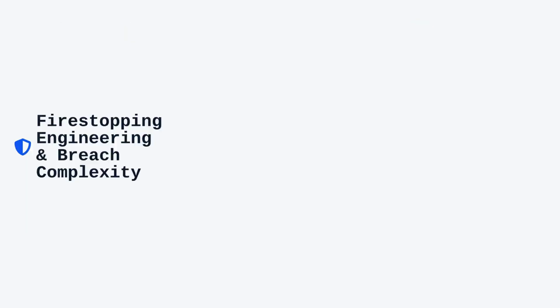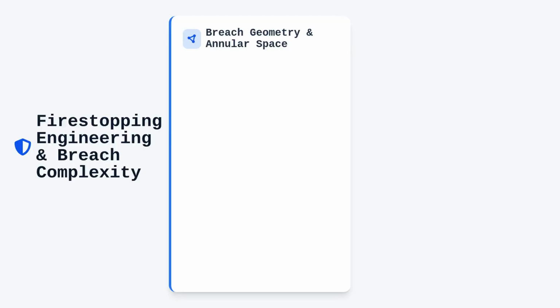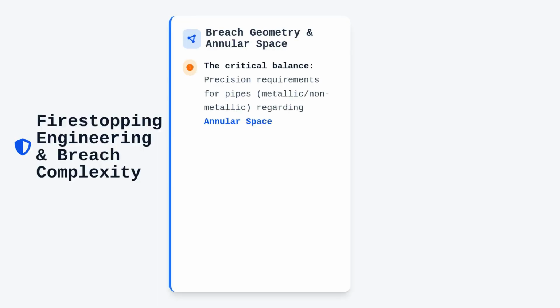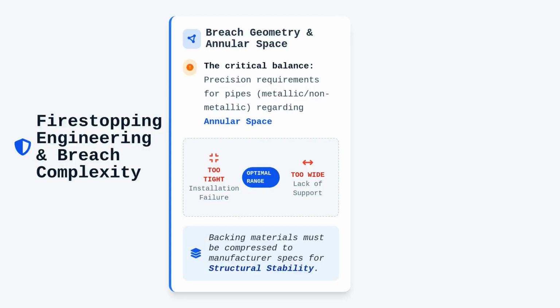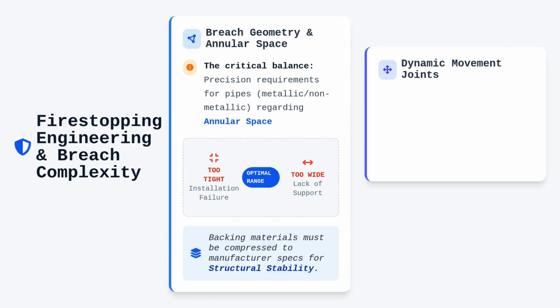The complexity increases when we consider the geometry of the breach. Through penetrations involving metallic or non-metallic pipes require precise annular space requirements, defined by the specific tested system. If the annular space is too tight, the material cannot be installed properly. If it is too wide, the material might not have sufficient structural support. This is where backing materials come into play, which must be compressed to the manufacturer's specification to ensure stability during the curing process.